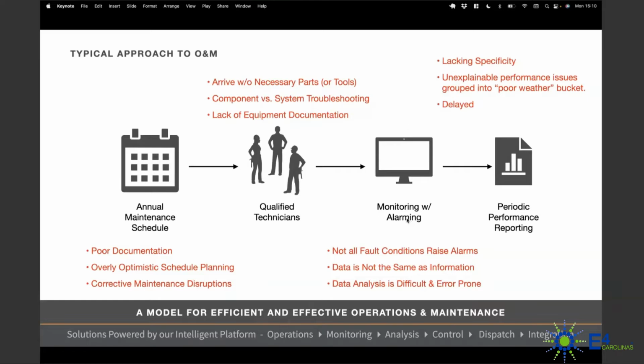The monitoring and alarming systems are very good at collecting data, but not necessarily providing information. And some of the conditions that arise on these sites don't necessarily render fault codes. For instance, a very basic one: if a medium voltage breaker trips, a trip is not really a fault, even though your site's offline. In fact, the breaker did exactly what it was supposed to do.